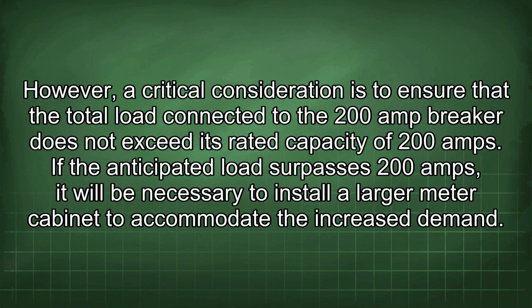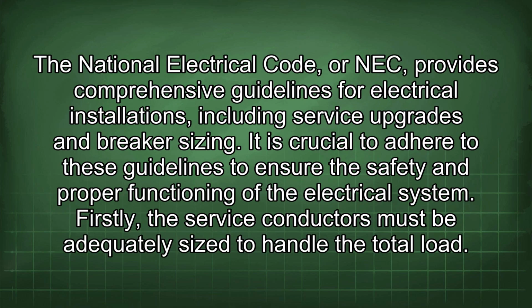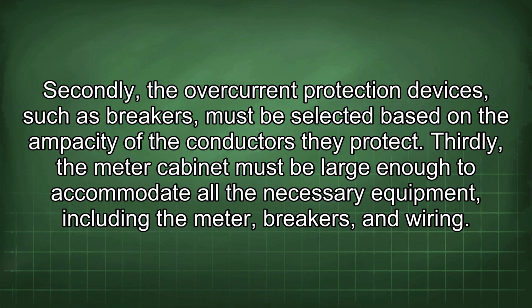If the anticipated load surpasses 200 amps, it will be necessary to install a larger meter cabinet to accommodate the increased demand. The National Electrical Code, or NEC, provides comprehensive guidelines for electrical installations, including service upgrades and breaker sizing. It is crucial to adhere to these guidelines to ensure the safety and proper functioning of the electrical system. Firstly, the service conductors must be adequately sized to handle the total load. Secondly, the overcurrent protection devices, such as breakers, must be selected based on the ampacity of the conductors they protect. Thirdly, the meter cabinet must be large enough to accommodate all the necessary equipment, including the meter, breakers, and wiring.